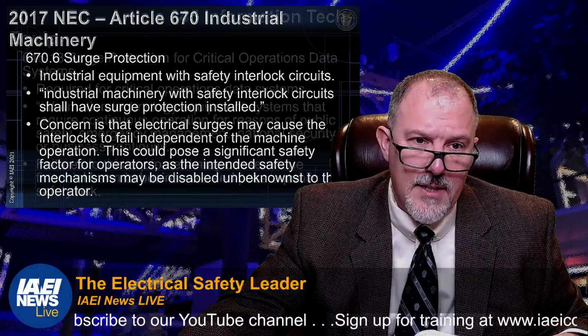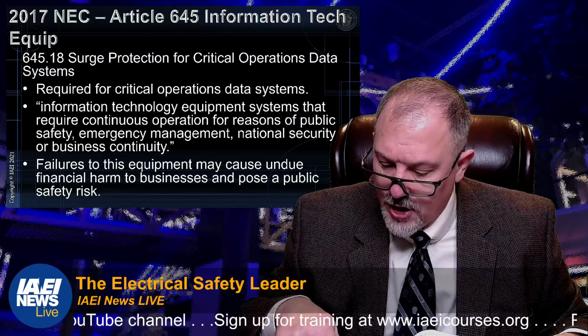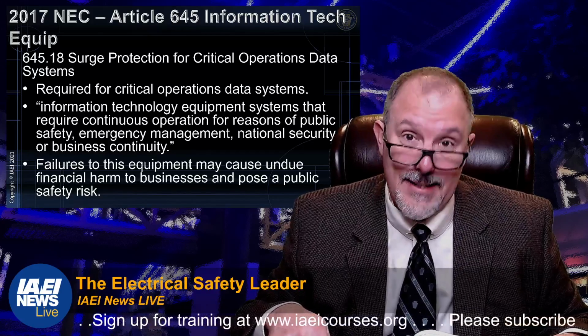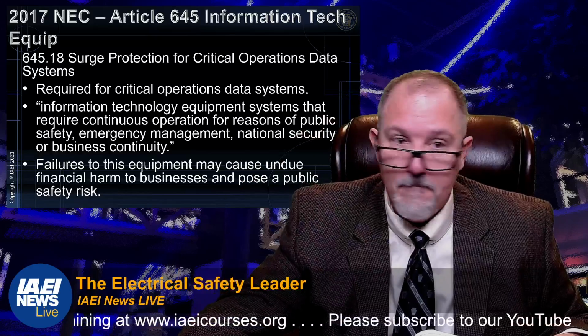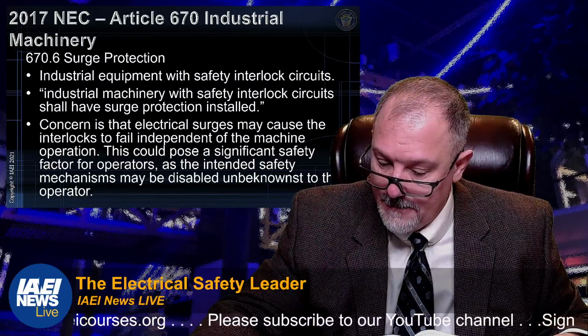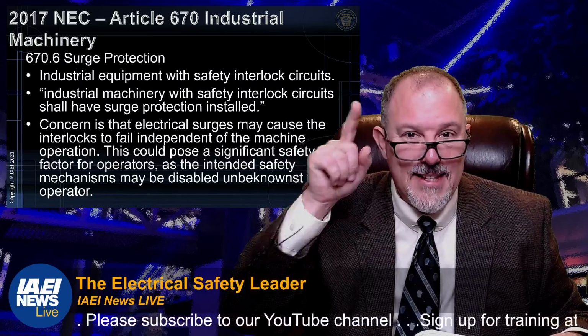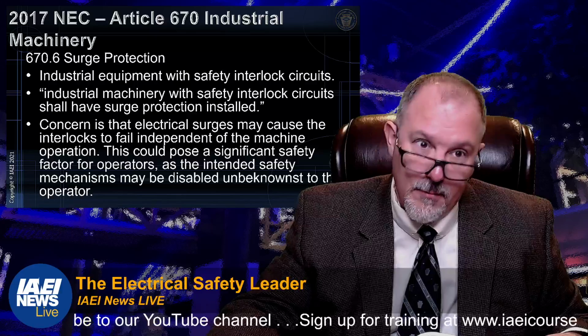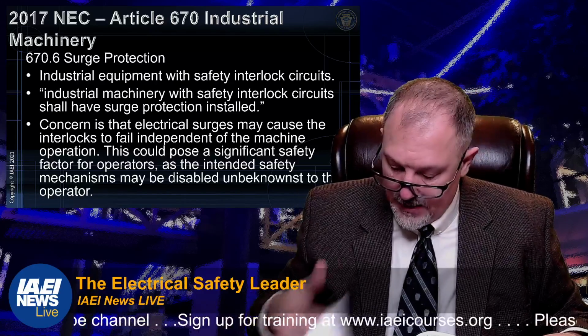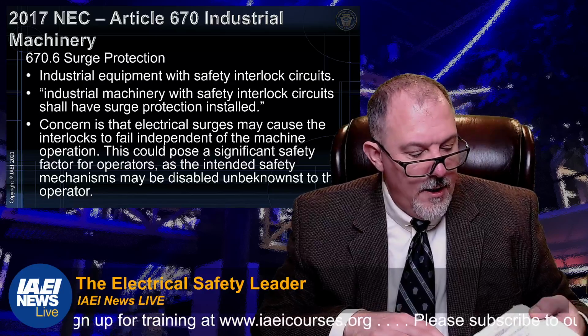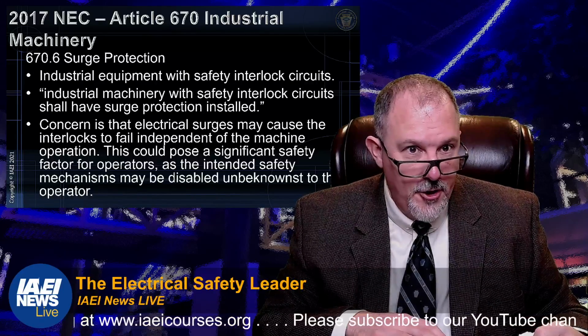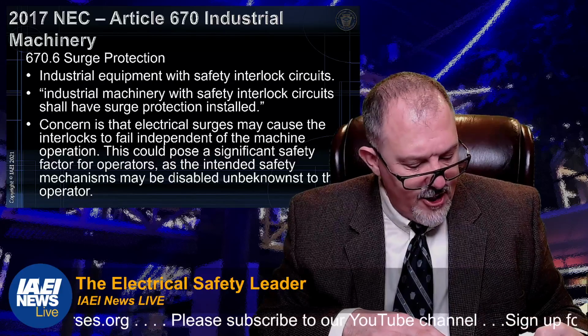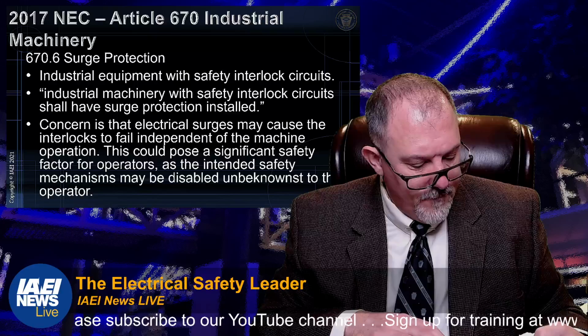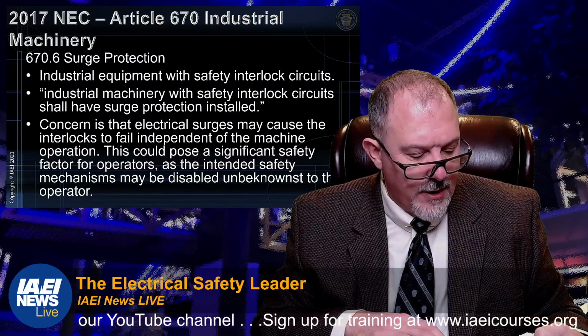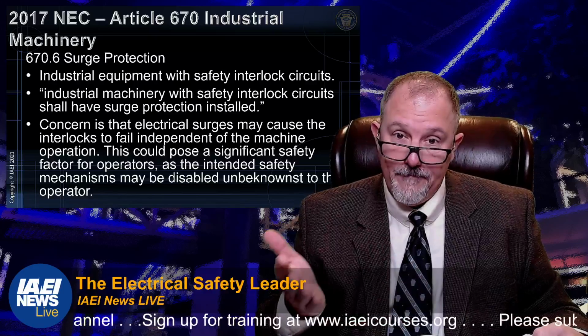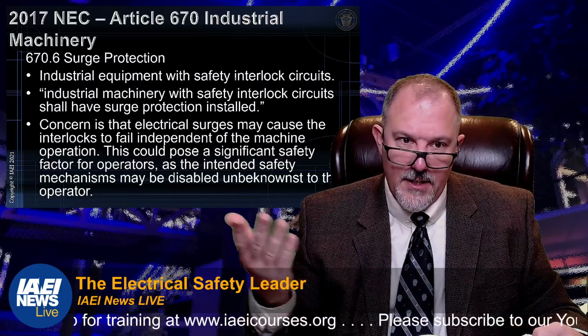670, that was when it was put in. So in the 17, they put that in. And the only change they made in the 2020 code was that it has to be listed. Big change. Has to be listed. 670.6. That's the other thing. I'm looking at the 17 changes, and I'm reading out of a 2020 book, so got to keep me honest there. 670.6. Now, 2020 made some changes here too, but this was new for the 17 code. Industrial machinery with safety interlock control devices not effectively protected from voltage surges on the incoming supply circuit shall have surge protection installed. So this is safety interlock control devices.